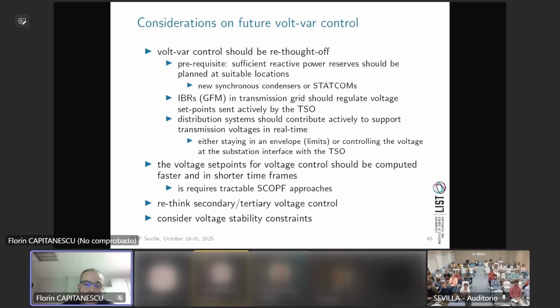With tertiary voltage control, you may calculate optimal set points for reactive power assets about an hour ahead. With secondary control, you'd look maybe every 10-15 minutes ahead, at specific pilot nodes, to control voltages.